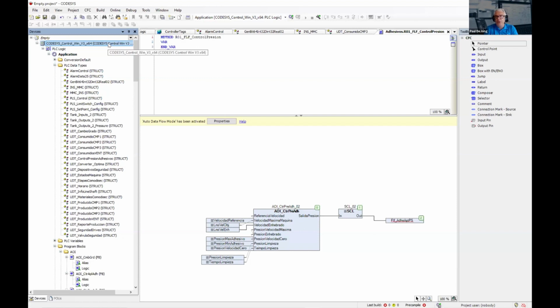We purposely do not convert the I/O tags inside. We carry the same name across so that the compiler will highlight that for you, and you can go in and change the names. You would need to remap the I/O to the I/O for your PLC. That's going to be part of the process.